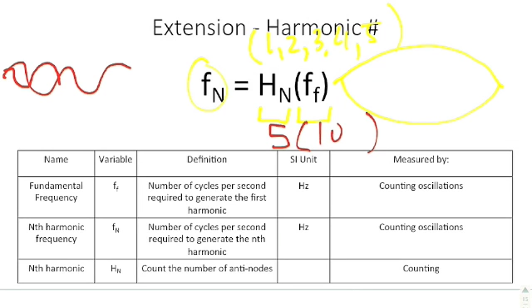So let's say I'm looking for the fifth harmonic. I would take 5 and multiply it by whatever the fundamental harmonic was, say it's 10, and I would expect to find the fifth harmonic, 1, 2, 3, 4, 5. I think I drew the 5 there. I would expect to find the fifth harmonic at 50 hertz. So that's a relationship there. It's kind of a direct relationship. So once you find the fundamental frequency, you're in good shape trying to figure out the rest of it.